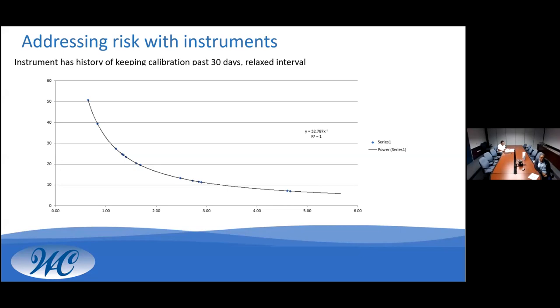As demonstrated before, one shoe doesn't fit all, and the default function proved to be still too tight or relaxed for some instruments. Good scores decrease the instrument's risk value, resulting in the algorithm calculating the interval using a relaxed function similar to this, with a good score allowing calibration interval over 30 days. This decreases unnecessary work done by analysts and allows resources to be diverted to more problematic instruments.